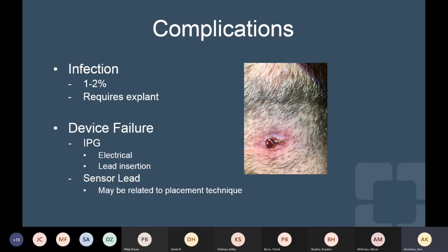You can get device failure. Sometimes the implanted pulse generator has electrical issues. Sometimes the leads are not inserted well. And sometimes you have problems with the sensor lead, which they think may be related to where we're grabbing it as we implant it. So here is a patient of mine who got one of the first or second improved devices, the 2nd generation device. And when that came out, they really didn't give guidance of how it was different and how to insert the leads. So this is a working implant, and this implant is not working.